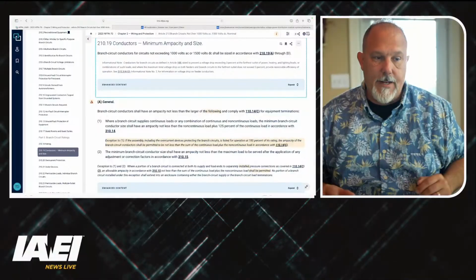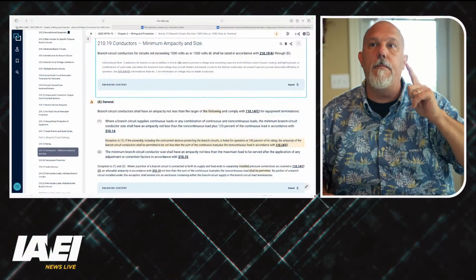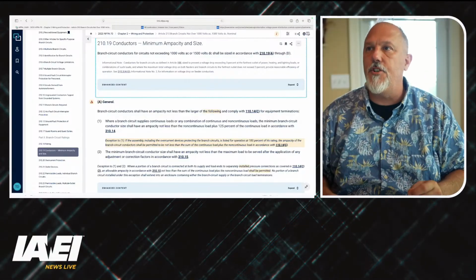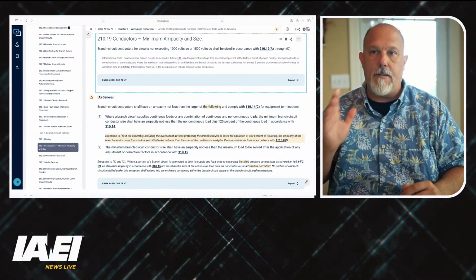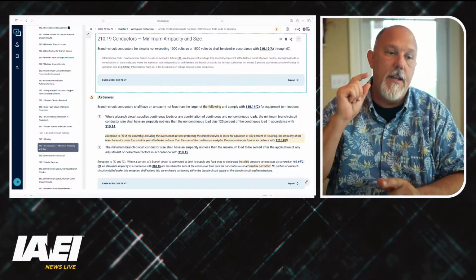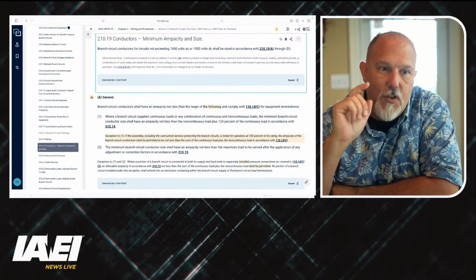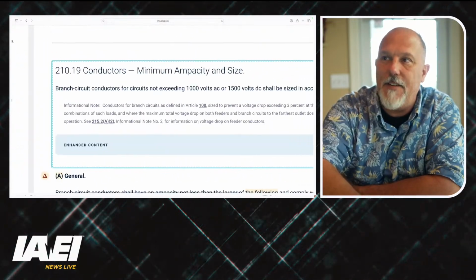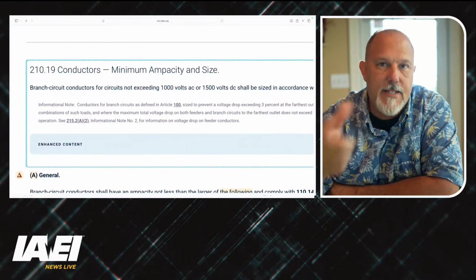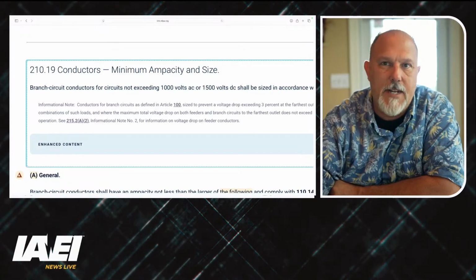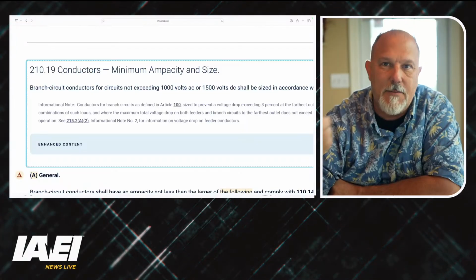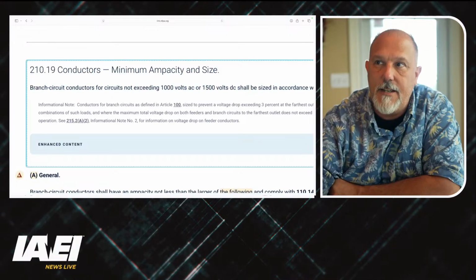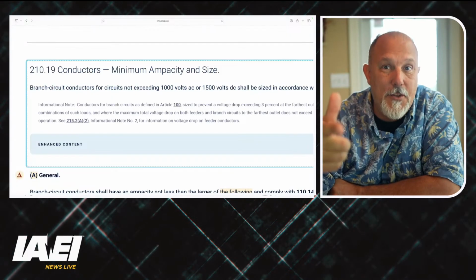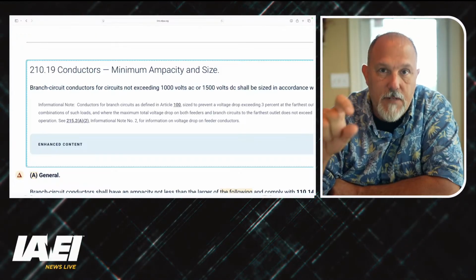We have a requirement in 210.19. I'll use that as the example. And I should be able to move my water and come over here. All right, in 210.19, and hopefully you have your copy or your link to NFPA LiNK open. I'm going to show you a few things that you may or may not have known about LiNK, because we can open multiple windows, and I'm going to show you that as we go through this discussion. But in 210.19, if you recall, and I have it in my notes that I said, and somebody had made the comment, once you have minimum ampacity, you don't need to worry about size, because that will dictate the size. So we talked about possibly changing the title of 210.19 to just say minimum ampacity. And that would be 100% wrong, and I'm going to tell you why in a second here. And we're going to do some examples.